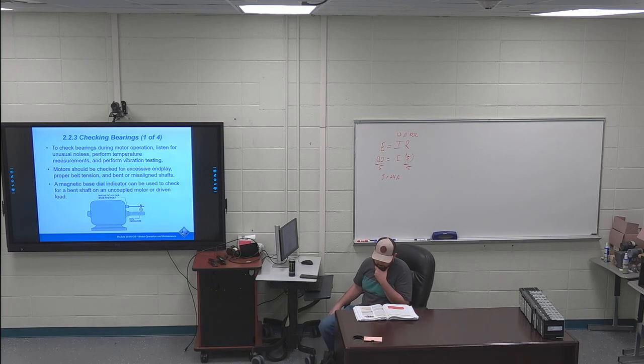On the right-hand side of page 13, right after that note, the first sentence is highlighted: motors should also be checked for end play. That's the shaft of the motor, how much it moves in and out, which is the backward and forward movement of the shaft. I've got to read the rest of the sentence. They go through the steps on how to check for end play and moving stuff around.